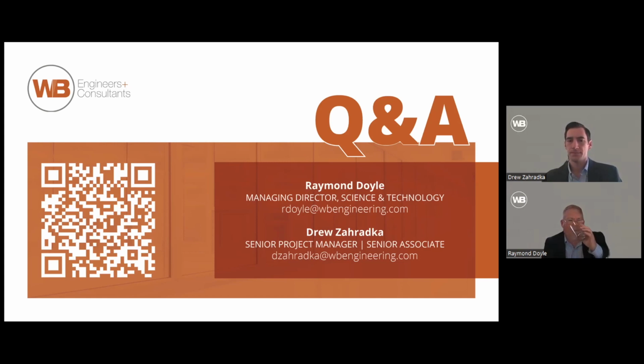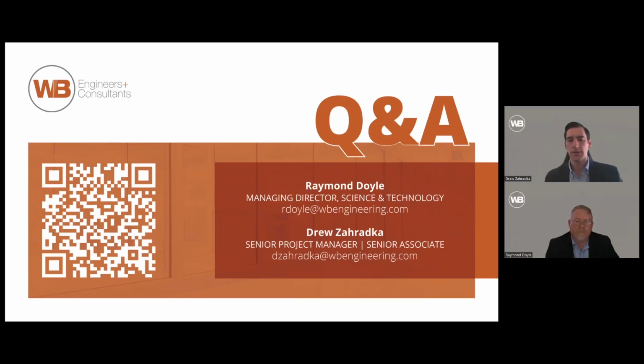Hey, Drew, this is Stephen Peterson with 35 North. Thank you guys for a good presentation. The fan filter units that you were just mentioning that you could swap out, would that be to provide the additional power to overcome the pressure drop across that local HEPA filter in a case where the air handler might not be able to push through? Yeah, that's the exact reason. If your existing air handling unit has a lower external static, you need that additional fan at the fan filter unit to overcome the HEPA pressure drop at your diffuser level. So it'll all be within the room, and it's pretty much just a booster fan to get the external static across that filter.